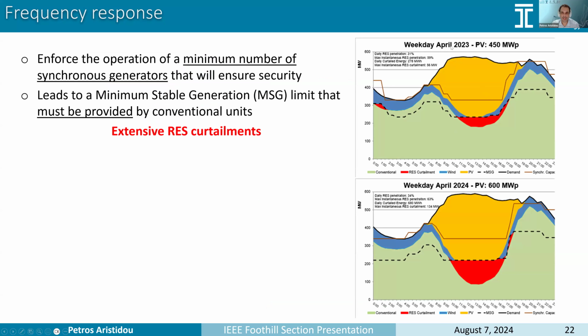If we see here different scenarios, this is a weekday in April where we see the conventional, wind and PV generation in the system, and the black dotted line is the minimum stable generation limit defined by the committed generators. And we see that in certain hours of the day, we need to curtail renewable energy sources in order to comply with this minimum stable generation. And this was in 2023. This is the same day in 2024.